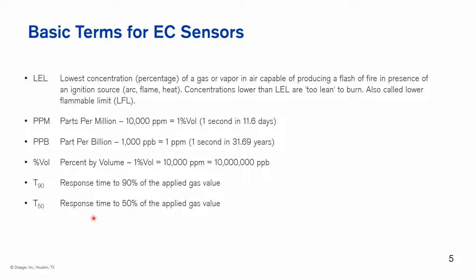When we talk about electrochemical sensors and toxic gases, we talk about parts per million. And just a quick reference there, to break down 10,000 ppm is 1 volume percent, or 1 second in 11.6 days. As we move forward in time, requirements for detection are getting much tighter. There are exposure limits around the world that are dropping like crazy. And so that's forcing our development to look more at what we can do down in even the parts per billion range. So that's where kind of the future of some of these toxic gases is headed. There's electrochemistry, but there's also other technologies that can get us down into that parts per billion range for a number of different compounds already.